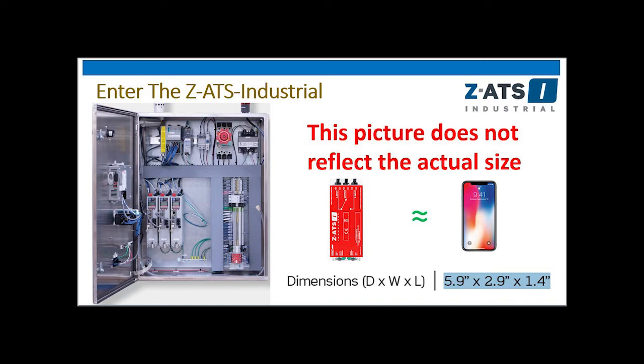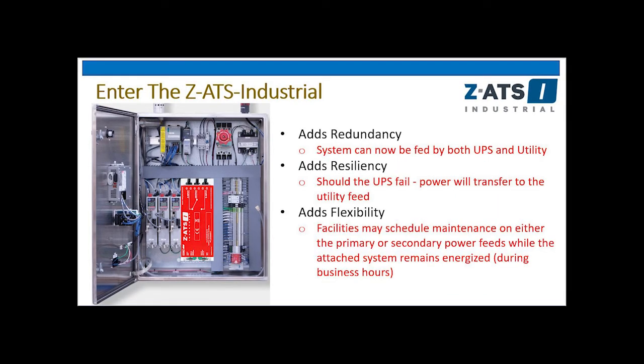People are using them because they add redundancy. Now those systems attached to this can be fed by both the UPS and the utility. If something happens to either feed, our industrial unit will bounce to the alternate feed, and the attached system remains energized, continuing to operate as if nothing happened. Adding in that resiliency is great because, no matter what you're doing out there, the redundancy and resiliency provide that operational continuity.